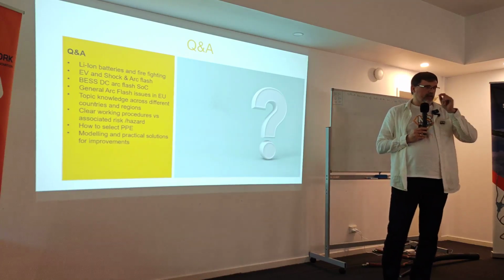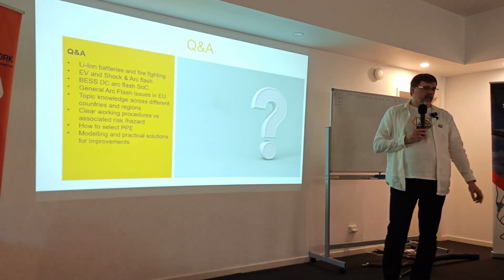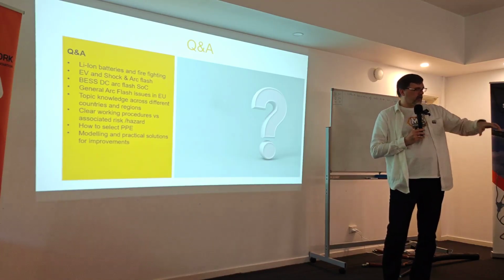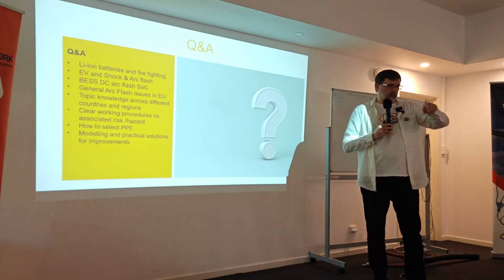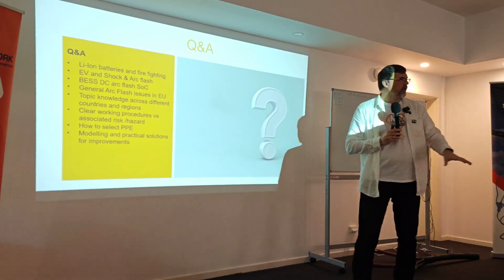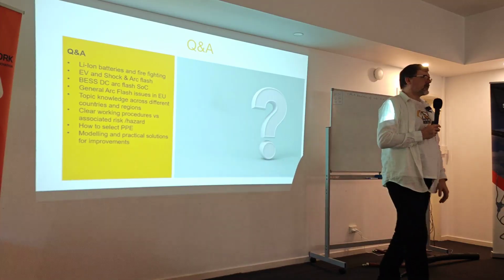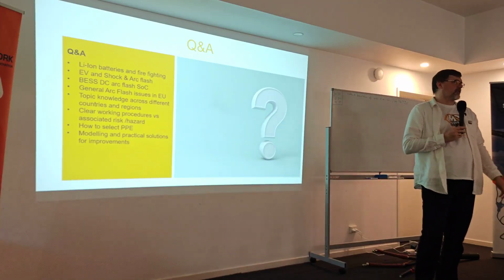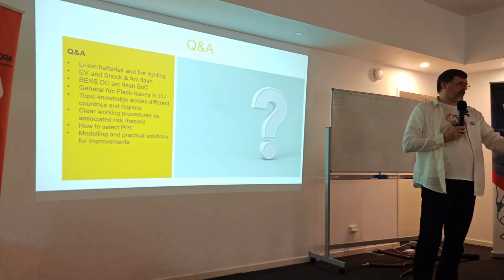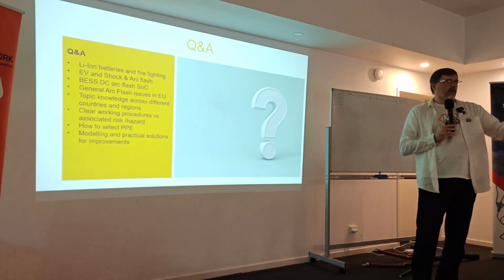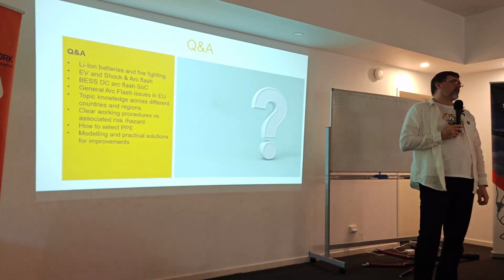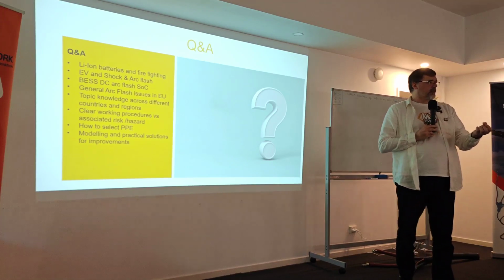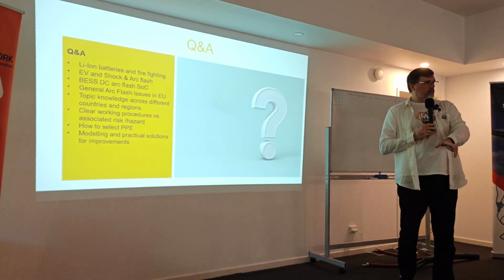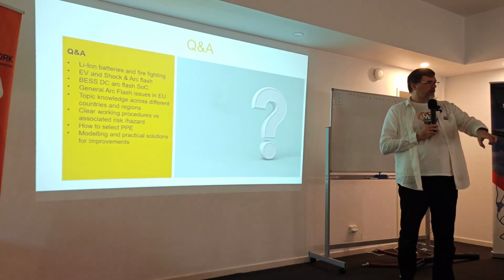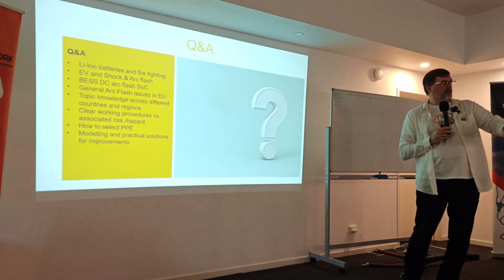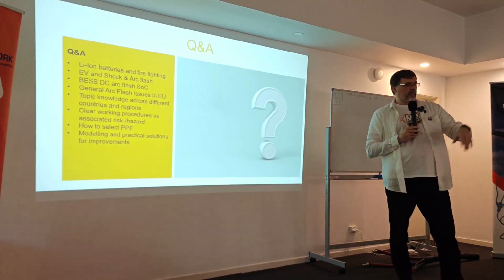And still they had one more accident because I missed one step which I wasn't aware of. They were assembling the packs in groups, and they went with the full battery for a long time. At one point, because they were not fully charged, I spent like 2 hours measuring those batteries, walking around. We also found out that they have something like a kill stop in between the batteries. They split the battery in 2, and in between there was a contactor, like the one that stops the power when you hit the car, the dynamic one.